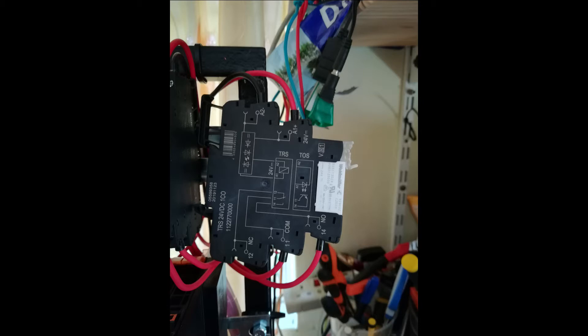They are used to switch on high current loads. For example, we can have huge pumps which result in high current devices. But a PLC output cannot drive the pump directly. We have to use signal relays to power contactors in direct online systems.